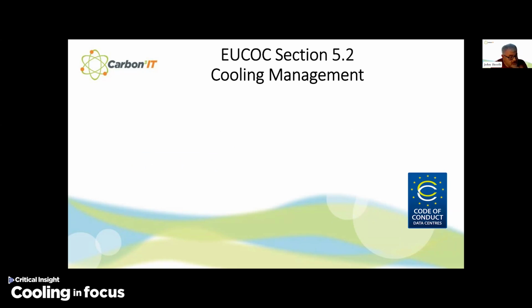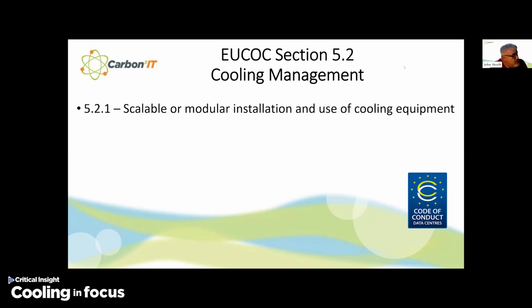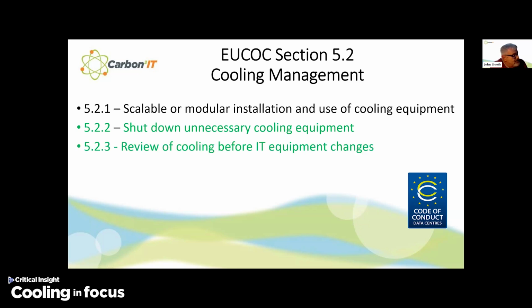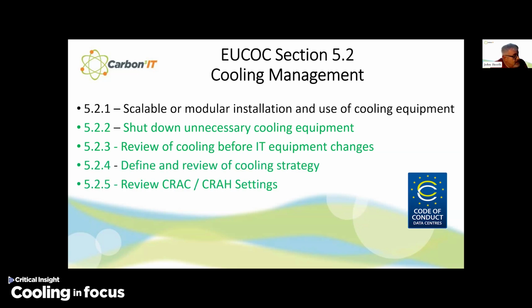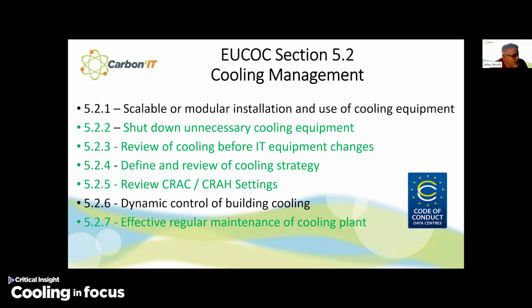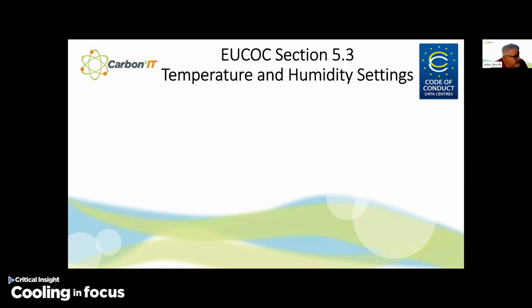Let me move on to cooling management. So scalable and modular installation and use of cooling equipment, shut down unnecessary cooling equipment, review your cooling before your IT equipment changes, define and review your cooling strategy, define and review your CRAC settings. An optional best practice is the dynamic control of building cooling. One really important one here, effective regular maintenance of cooling plant, and that will touch upon our ticker stuff in a moment. Review and optimize your chilled water temperatures.